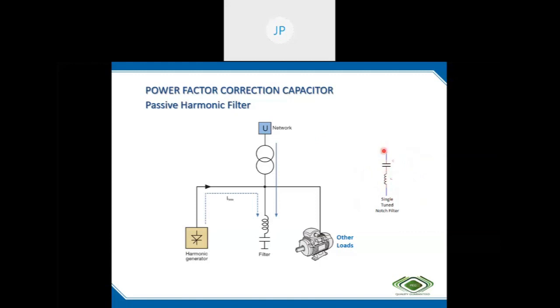A detuned bank is not intended to carry the harmonic current or take care of the harmonic voltage, so its rating will be less. So we cannot use the same design for the harmonic filter. A filter is connected, with a normal load and a nonlinear load. This is low power factor, so we need improvement, and we have to connect the capacitor. So we make a single tuned filter for the fifth harmonic, and the harmonic current will flow through this one, because the impedance for the fifth harmonic is zero here.